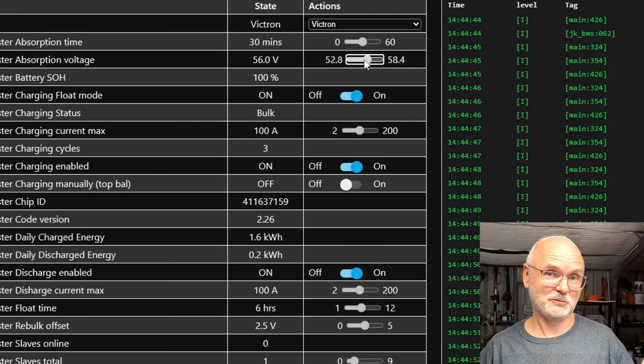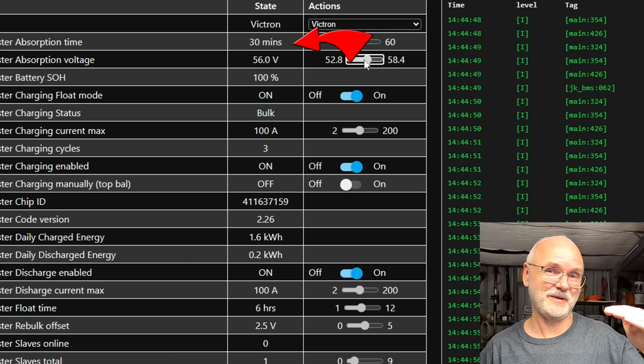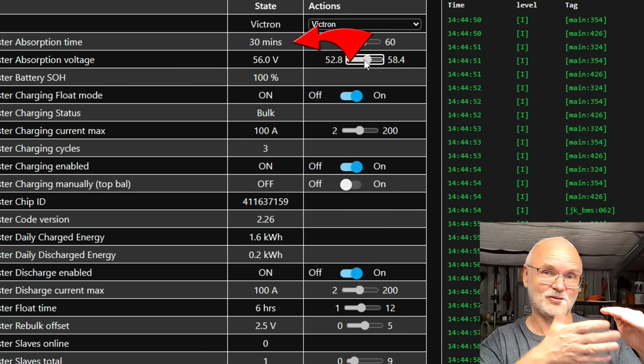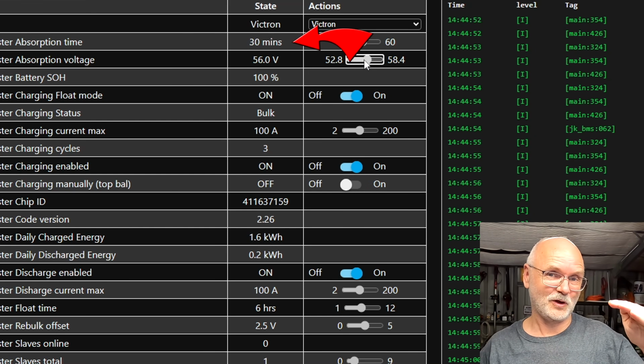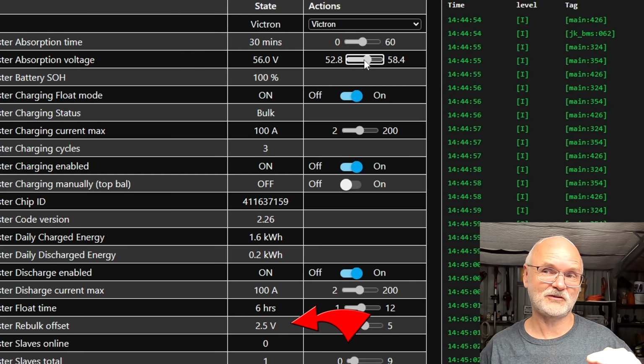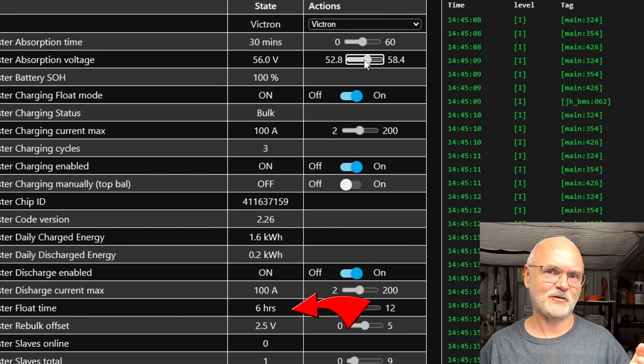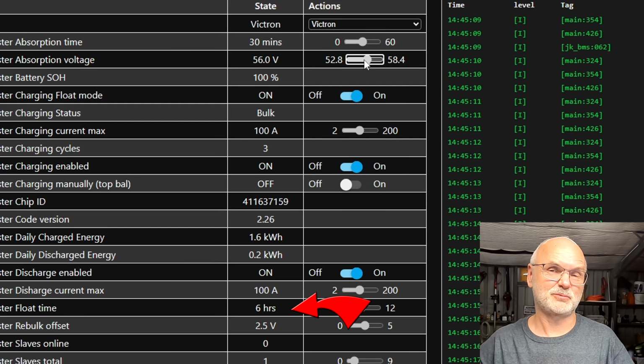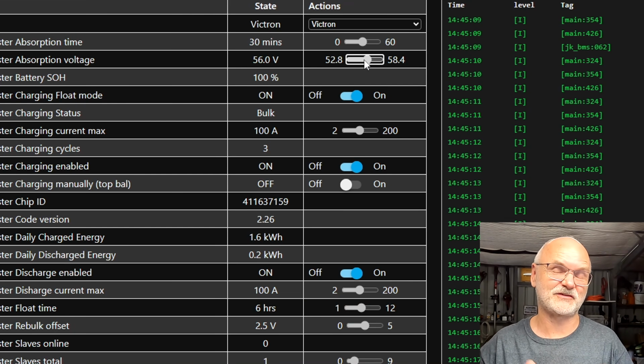So your inverter would charge the battery to 56 volts, hold the voltage there for 30 minutes to allow the balancer to do its job, then lower the voltage by 2.5 volts to a float voltage, and keep this float voltage for 6 hours. It keeps the battery 100% charged at a lower voltage. Then after 6 hours, presumably after sunset, it starts a new cycle, and the next morning it will charge to 56 volts again. So can your inverter do that?